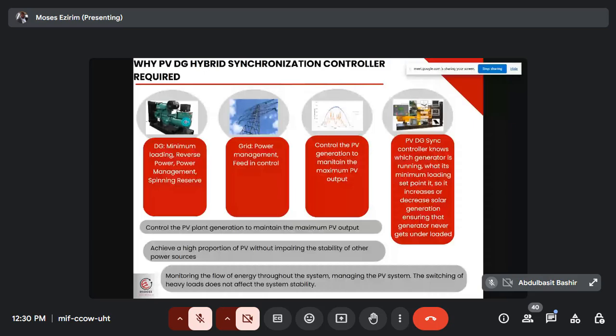But the function of the controller in the grid is to manage power sending to the grid. That's what we call feed-in control. The controller will help you with that. This is the main function. It controls the PV generation to maintain the maximum PV output. You can have 5 generators, you can have multiple generators. The controller knows which generator is running and what its minimum loading set point is.